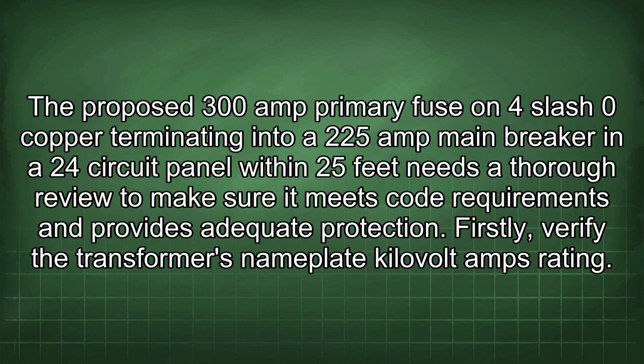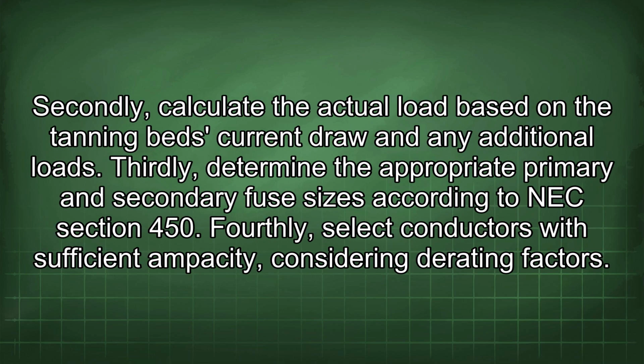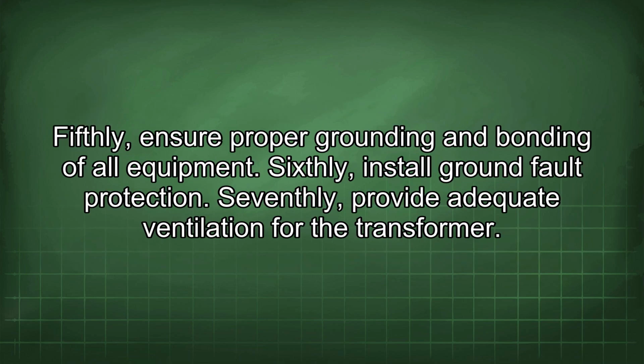Firstly, verify the transformer's nameplate kilovolt amps rating. Secondly, calculate the actual load based on the tanning bed's current draw and any additional loads. Thirdly, determine the appropriate primary and secondary fuse sizes according to NEC section 450. Fourthly, select conductors with sufficient ampacity considering derating factors. Fifthly, ensure proper grounding and bonding of all equipment. Sixthly, install ground fault protection.